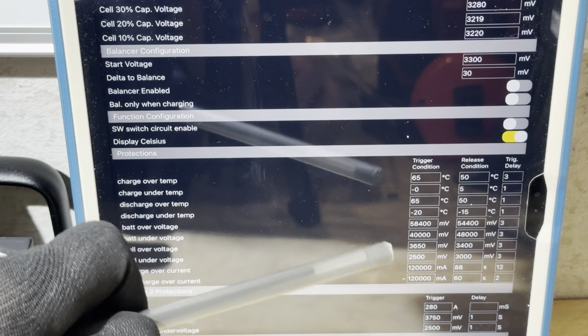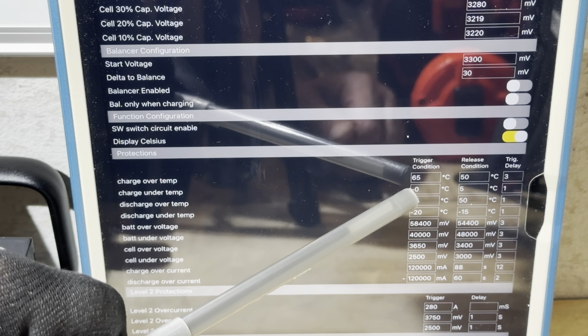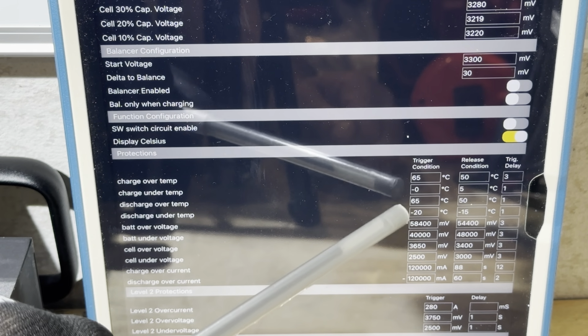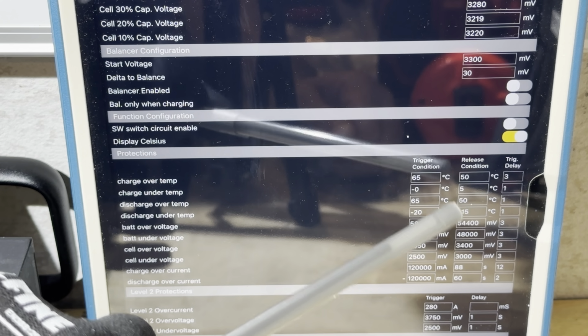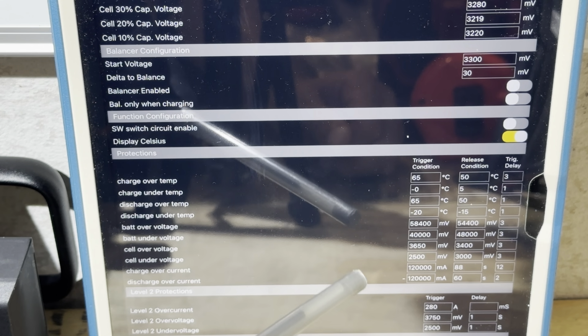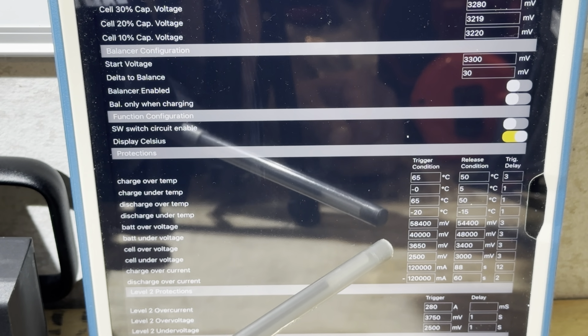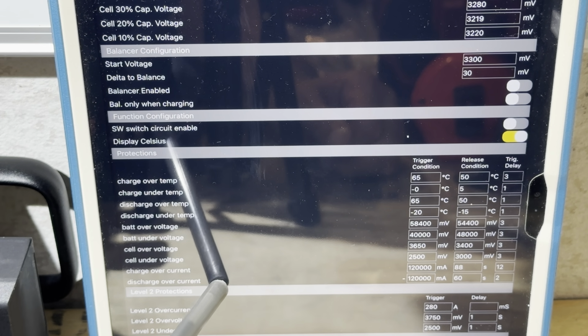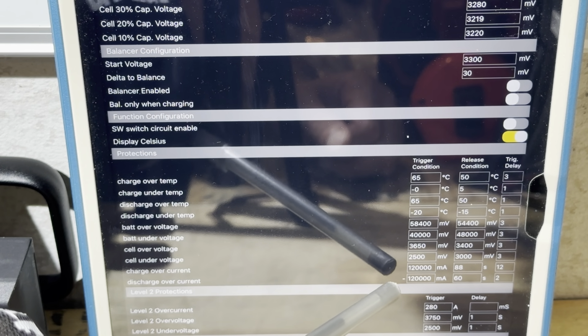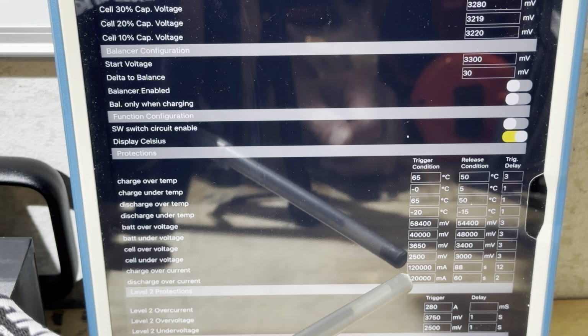If we look at our protection programming right here, the charge over-temp is 65C, the under-temp is set properly at 0 degrees C with a 5 degree C above release on that. So showing you some of their program values right here, and their charge and discharge current value is 120 amps.